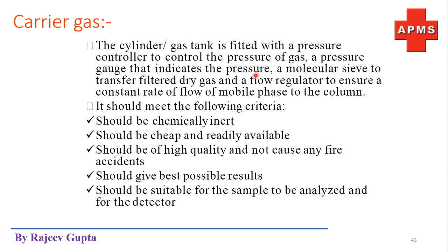Also, if we are not sure whether the gas is completely pure, meaning moisture free or not, then we can use a molecular sieve assembly in the flow of carrier gas to transfer filtered dry gas. These molecular sieves absorb the moisture present in the gas, filter it, and give a dry gas.